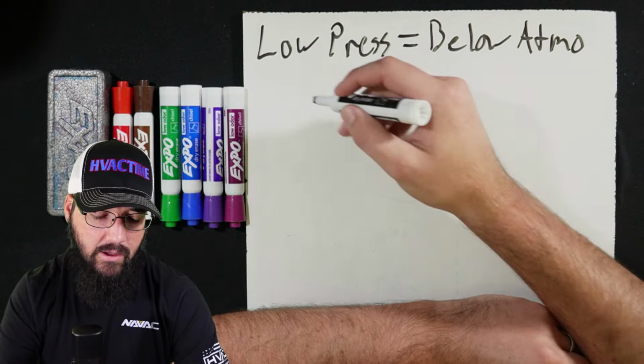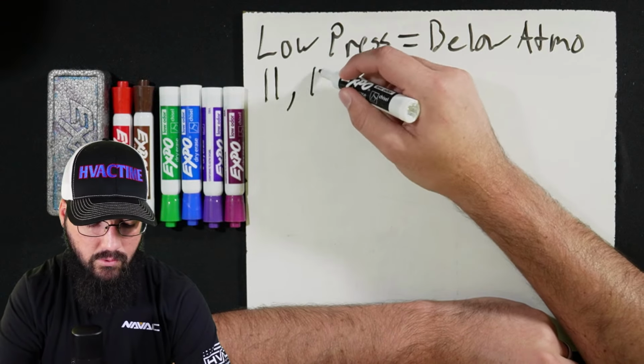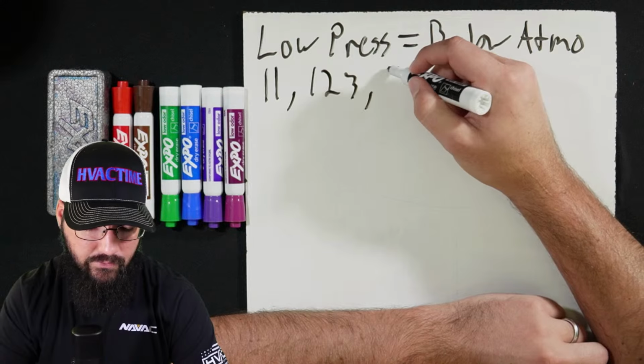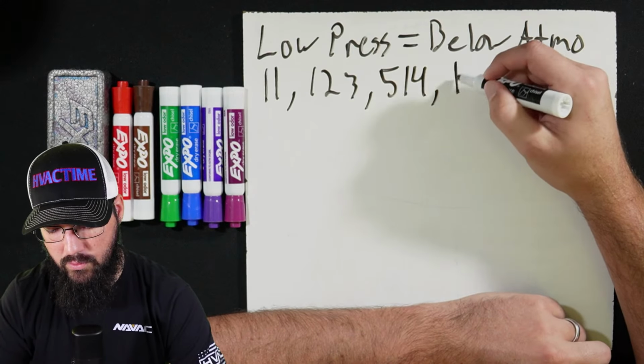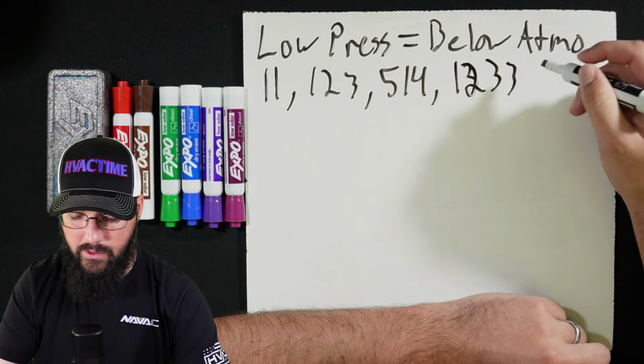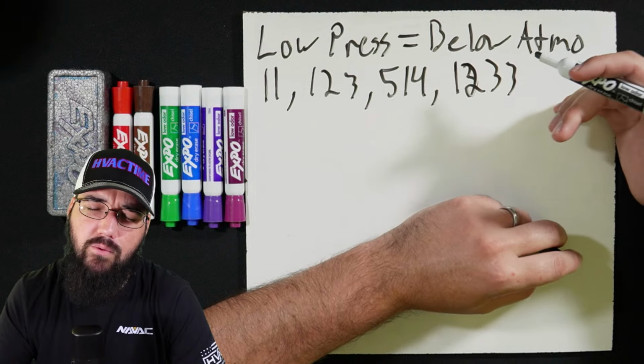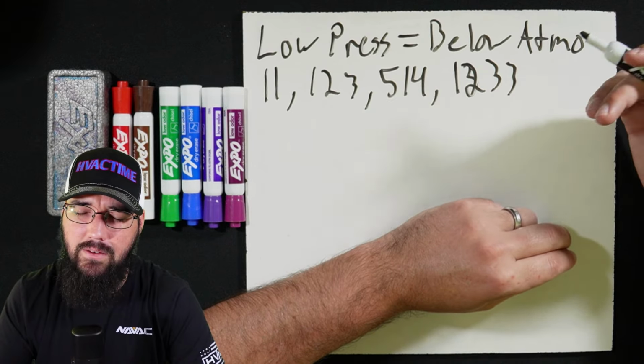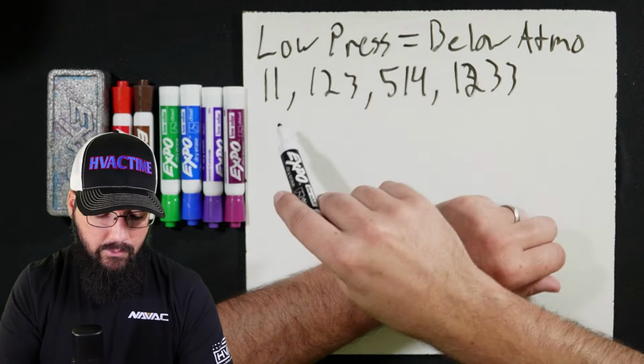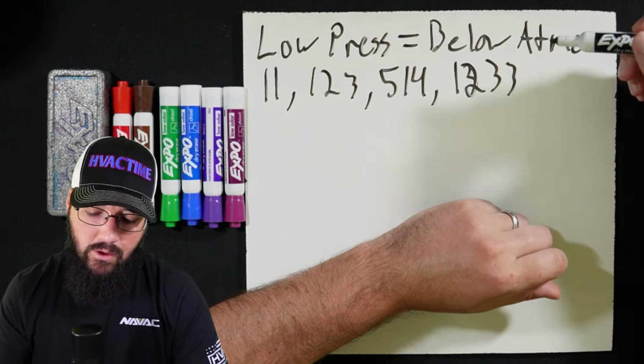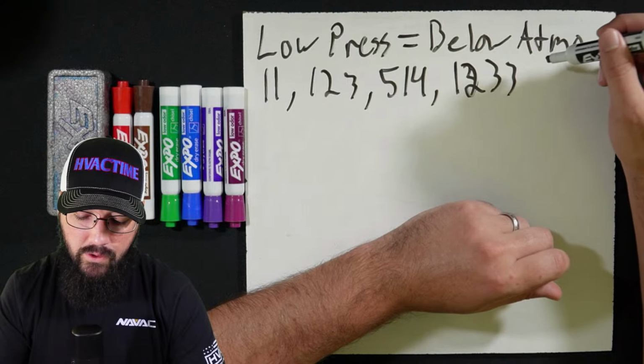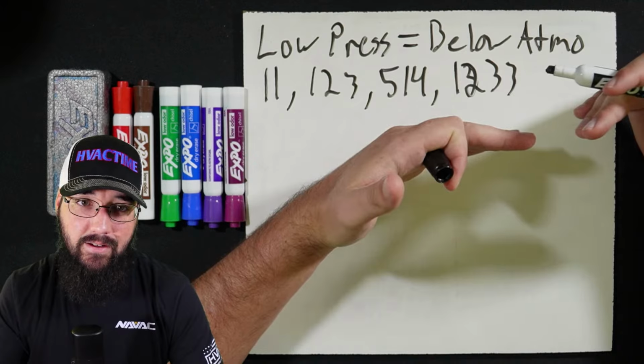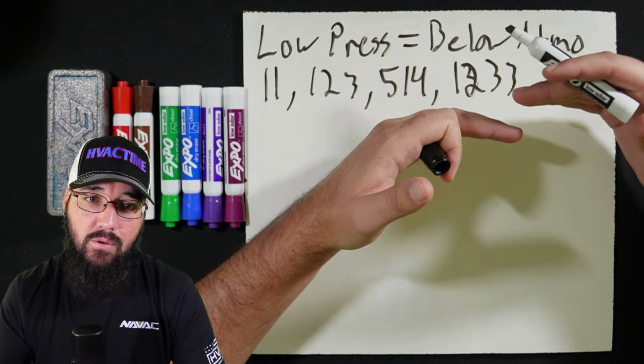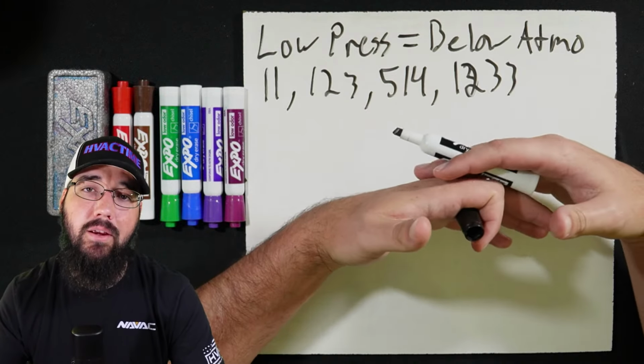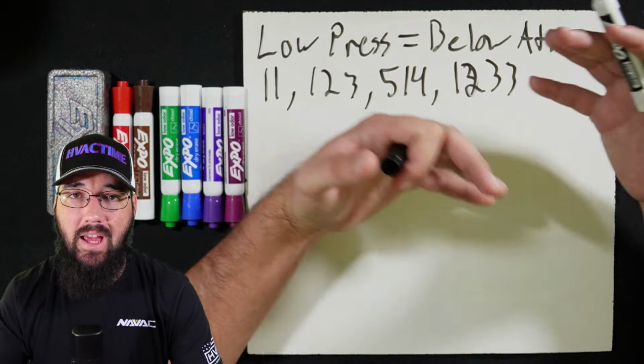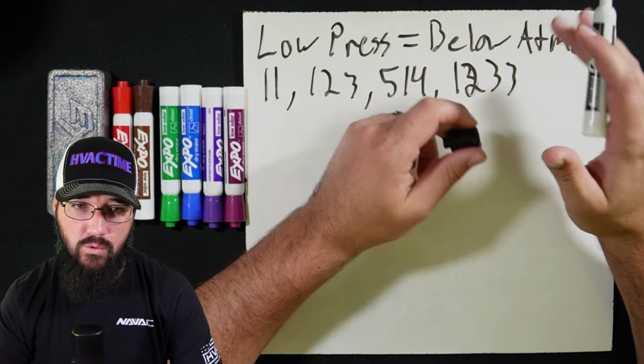These refrigerants are like R11 or 123 or 514, and then we have 1230. 1233 is another one. And then we have the 1234 YZD or YEZ or whatever it is that York's using. Anyway, these are some examples of low pressure. Now, one of the weird things about this is that at its standing, it is below atmosphere. So at ambient, many times our pressure is actually in a vacuum. This chiller sits in a vacuum and makes it very easy to draw non-condensables or just atmosphere into the refrigerant, which is going to contaminate it and cause a whole slew of problems.